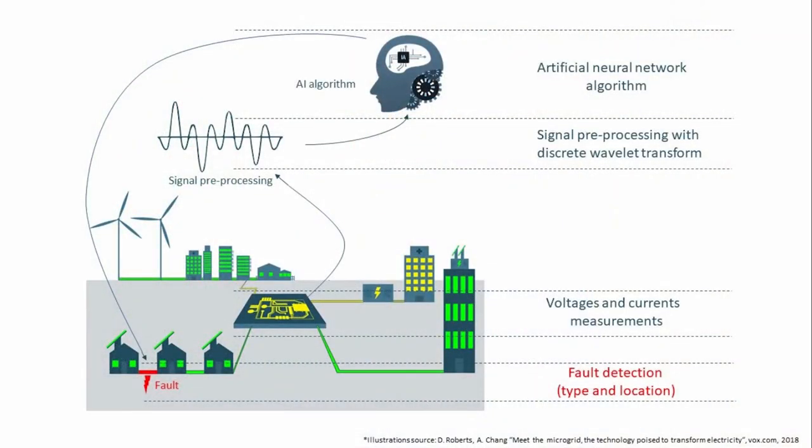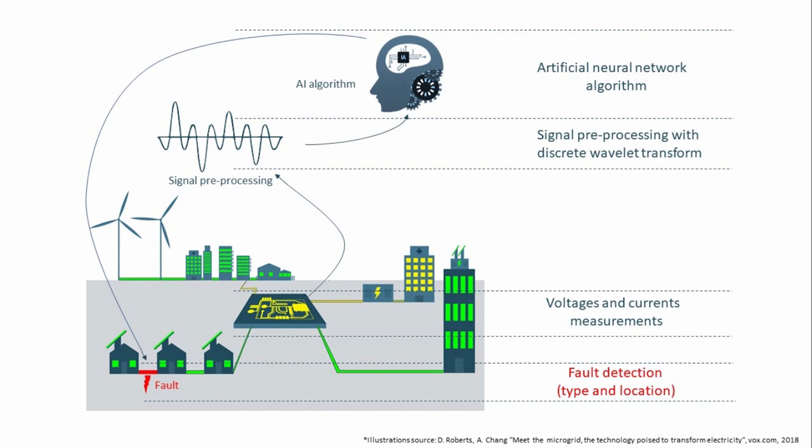And this is the topic of my thesis. Protection of microgrids that can work in both grid-connected and islanded mode is challenging, primarily due to the unpredictable and dynamic behavior of the microgrid. However, by looking at the voltage and current waveforms, valuable information about the system behavior can be extracted. Therefore, by using different pre-processing techniques — where discrete wavelet transform proved to be a promising one — I created a so-called signature signal that describes different events in the system.